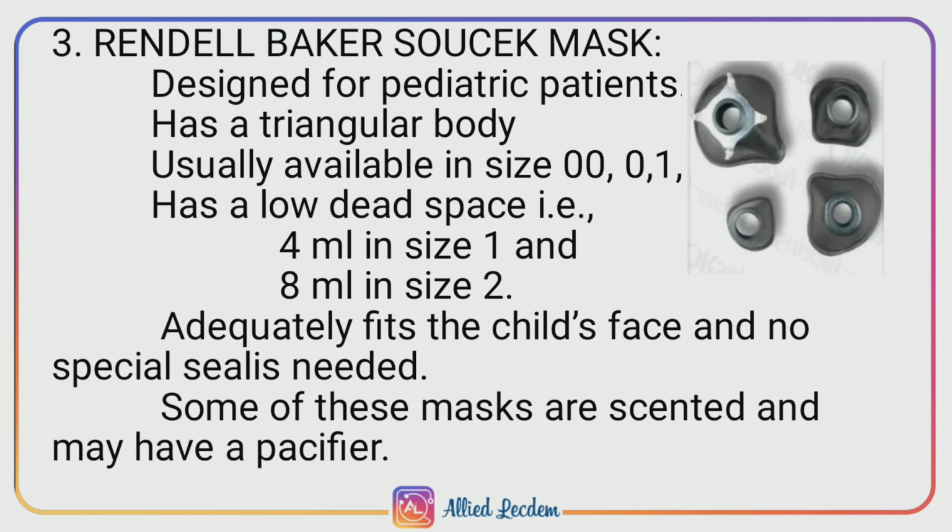Rendell-Baker mask. Designed for pediatric patients, it has a triangular body and the sizes available are 00 or 0. It has a low dead space, adequately fits the child's face and no special seals are needed. Some of these masks are scented and may have a pacifier.